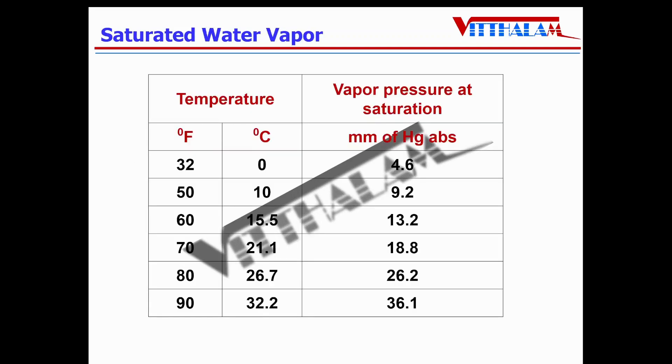So this is the table related to pressures versus saturation temperatures of the water. You can see at a pressure of 9.2 mm of Hg absolute pressure, saturation temperature is 10 degrees Celsius. It means if the air temperature is about 10 degrees Celsius, then the water in the air will always remain in the vapor form.